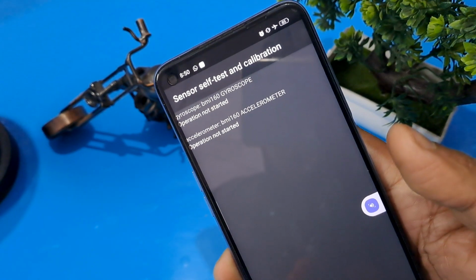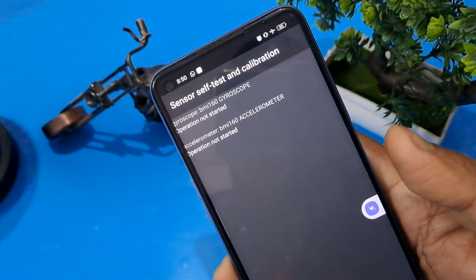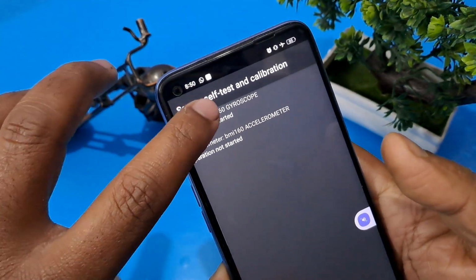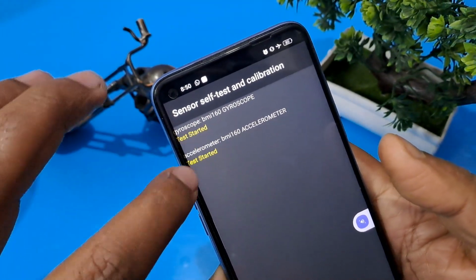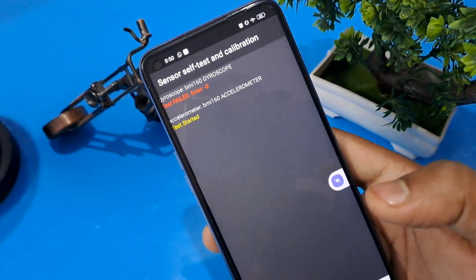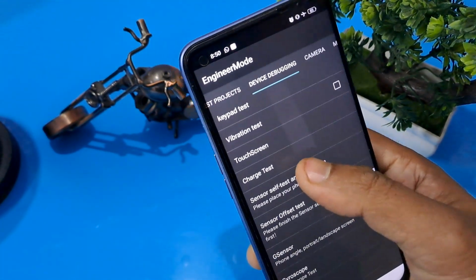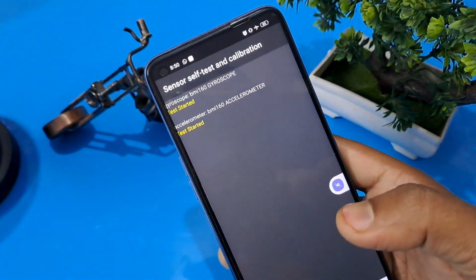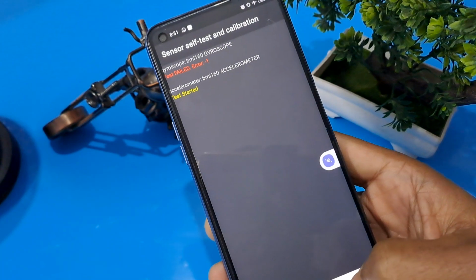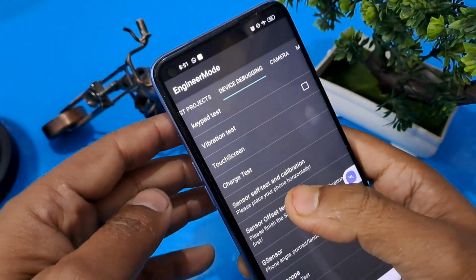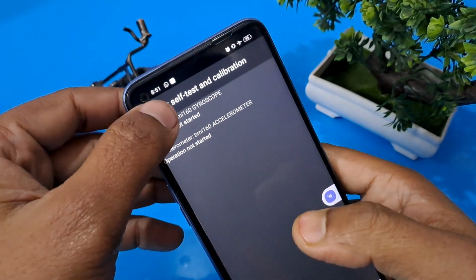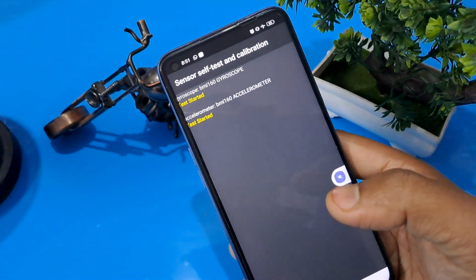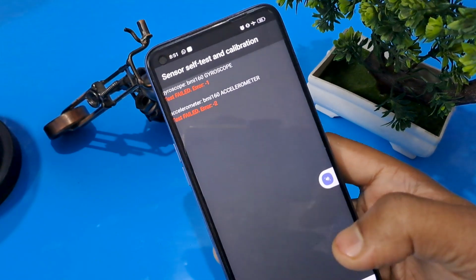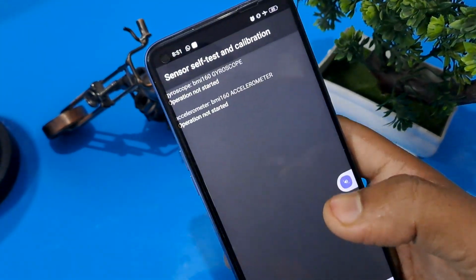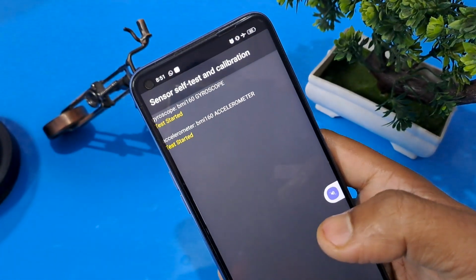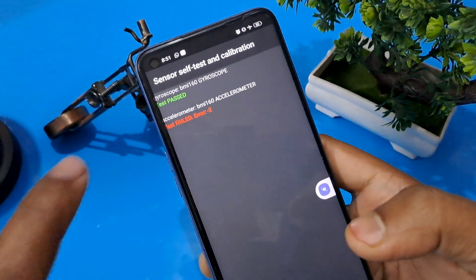Two options are coming, gyroscope and accelerometer, and both show operation not started. We have to press both options at the same time, and we have to pass at least one. Apply this method 2 times, 3 times, 4 times, no issue. You have to apply it till passed. Again we have to press till passed, so apply this method again and again. Now finally the text passed is coming.